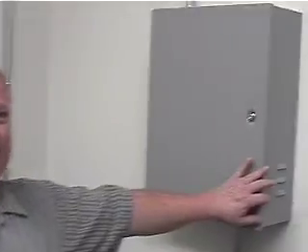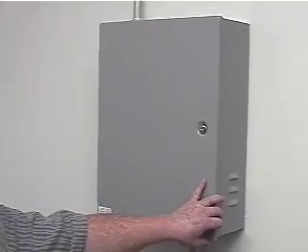All right, real quickly, as we're coming down, I just want to show you this building has a total of 2 NAEs. One of them is located on the 3rd floor of the telecom room, which is right here. This is an NAE 45. This is what communicates with the entire 3rd floor and 4th floor. Down on the 1st floor, we have an NAE 55 that communicates with the 1st floor and the 2nd floor VAV boxes and peripheral equipment. Everything except for the stuff that's in the mechanic rooms down in the basement.